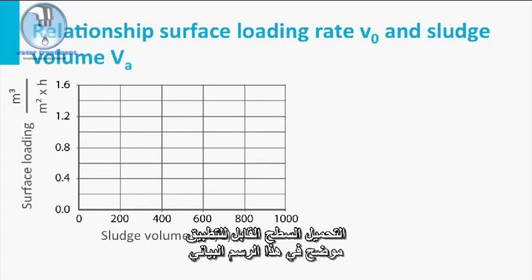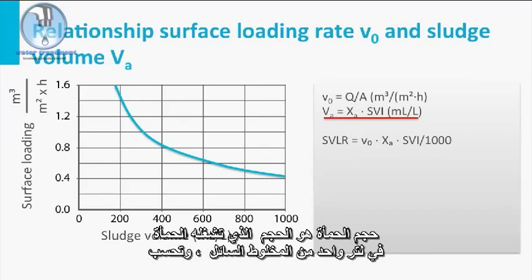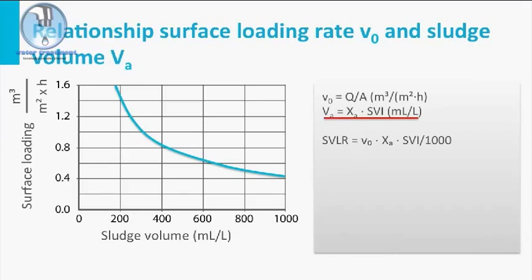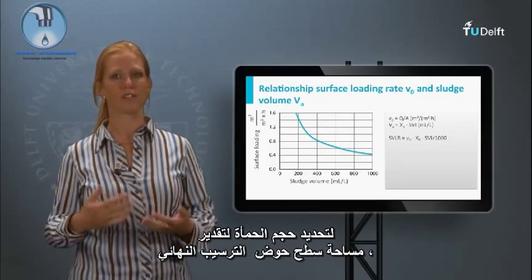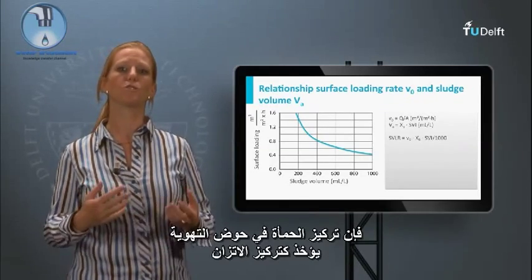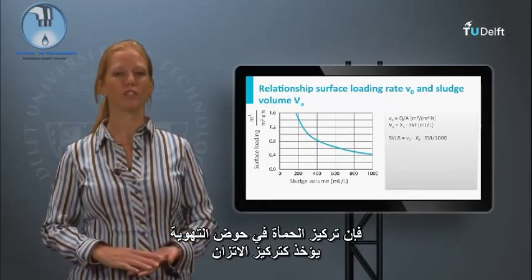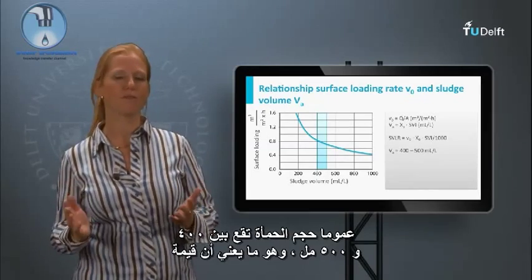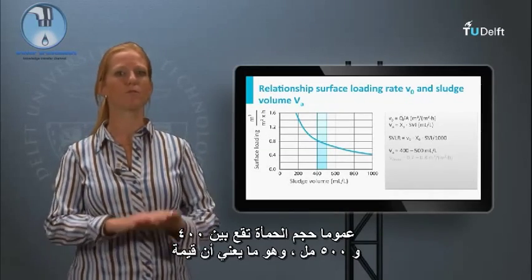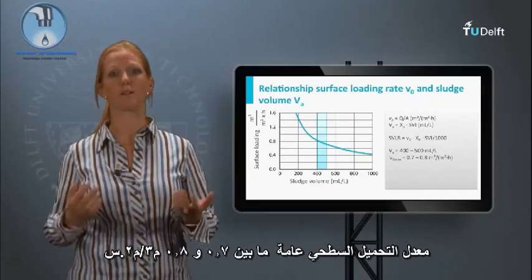The applicable surface loading is visualized in this graph. The sludge volume is the volume that the sludge occupies in one liter of mixed liquor, calculated by multiplying the sludge volume index times the sludge concentration. To determine the sludge volume and estimate the surface area of the final clarifier, the sludge concentration in the aeration tank is taken as its equilibrium concentration during stormwater flow. Generally, the sludge volume lies between 400 and 500 milliliters, which means that the general surface loading rate is between 0.7 and 0.8 cubic meters per square meter per hour.